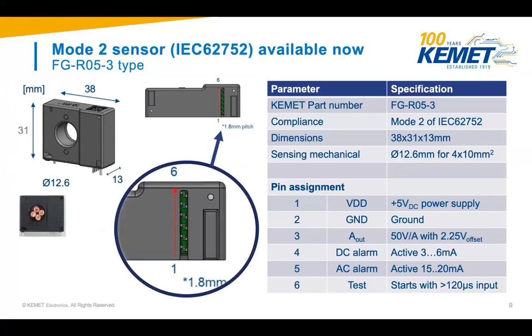The pin assignment is rather easy. Pin 1 is assigned to the supply voltage, which is 5 volt DC plus minus 5%. Pin 2 is ground. Pin 3 is an analog output with a resolution of 50 volts per amp with a 2.25 volt offset. Then we have the DC alarm active from minimum 3 to maximum 6 milliamps. In the worst case, the AC alarm is active from 15 to 20 milliamps, and then there's the test signal input on pin 6, which starts the test procedure when the input pulse is longer than 120 microseconds.